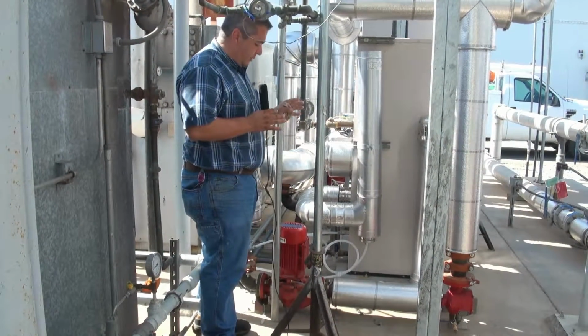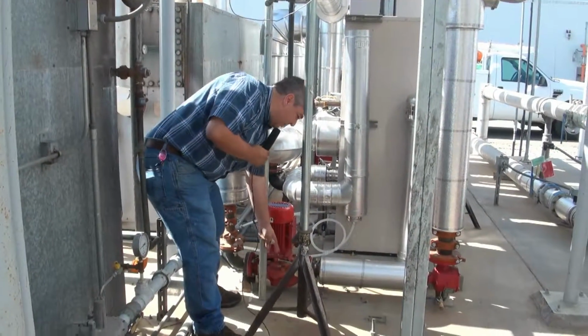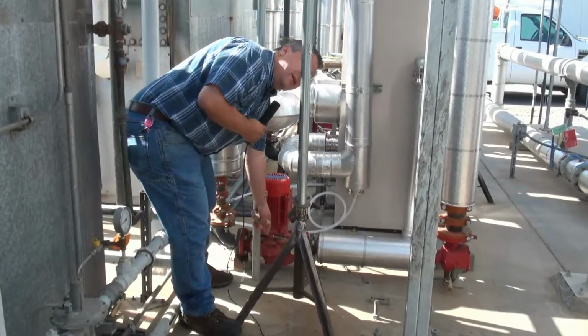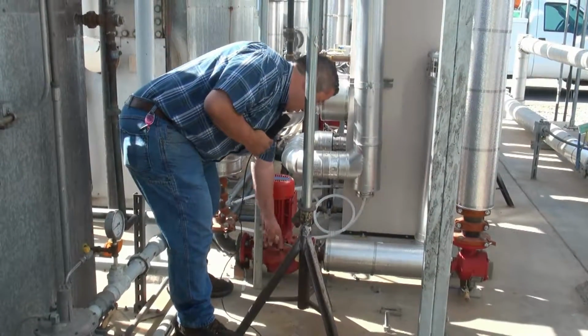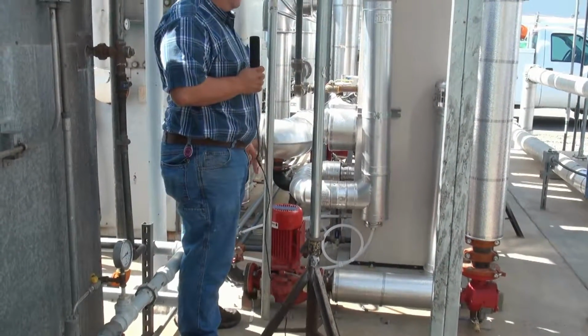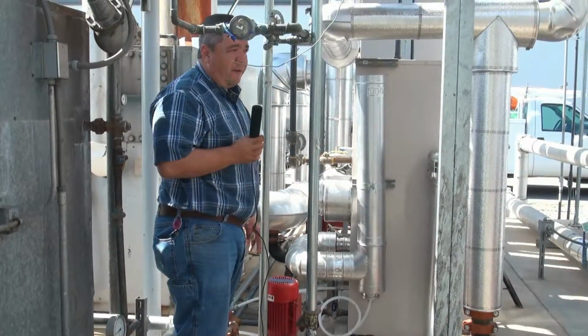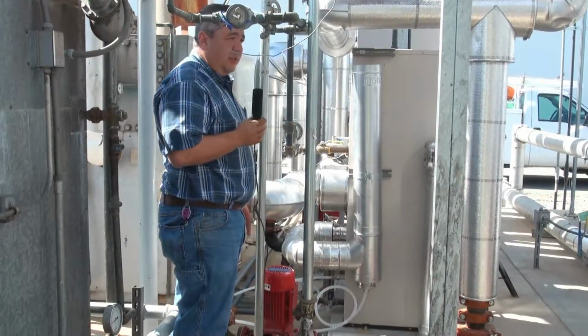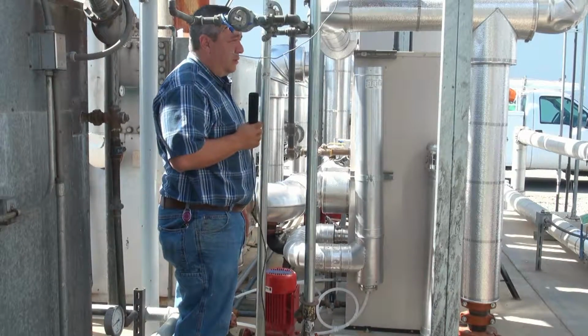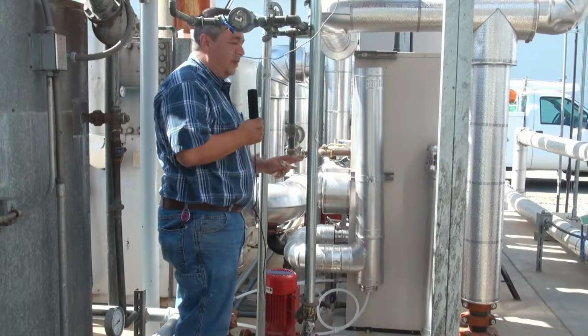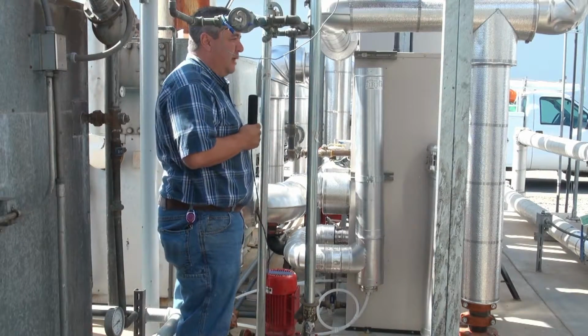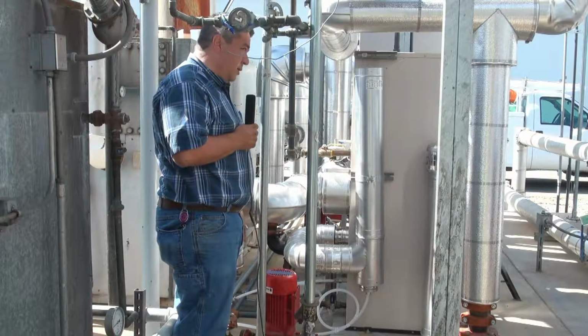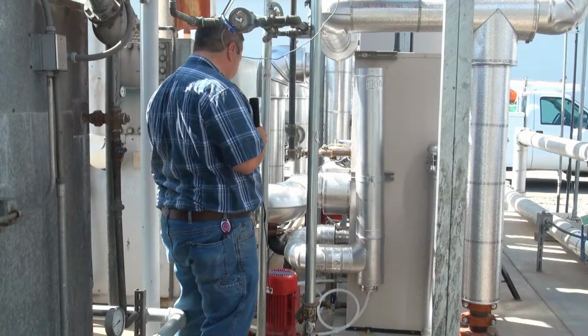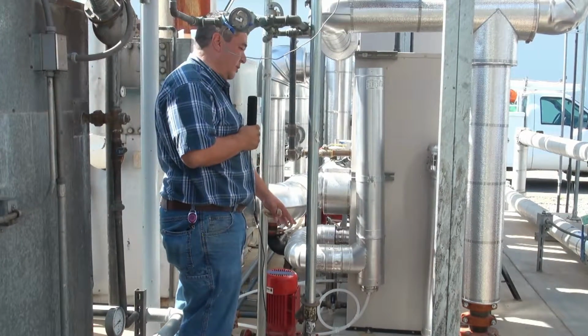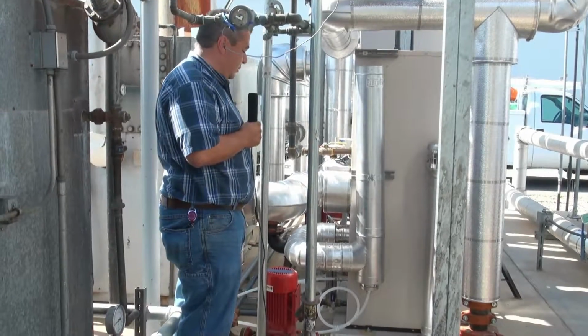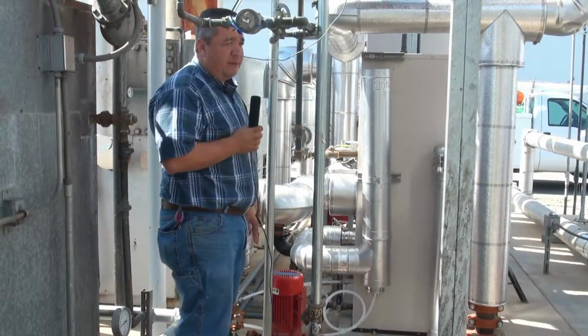So I was talking about, when we were inside, this little line here. This line keeps the bearings lubricated, brings water out, because they have to maintain water in them. So that's why it's important to make sure your water chemistry is good. Make sure there's nothing going on in those bearings, because otherwise you're going to... I'm sorry, the mechanical seal, not the bearings. You've got to make sure the mechanical seal is kept in good shape. That's on the discharge of the pump? Yep. No, on the suction, sorry. So we've got to make sure that your water chemistry is good, obviously, for those reasons.